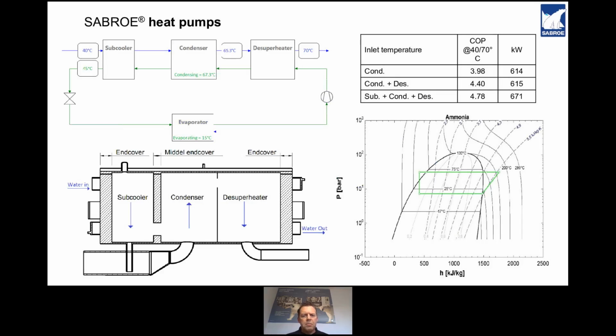So moving on to the next slide. How does it work? Here we go. Lots of diagrams, I apologize. Top left is the diagrams to look at. If you look at we have the compressor, the circle with the diverging lines on the right hand side of the top left diagram. We have that discharging hot discharge gas at about 130 degrees C. That enters the desuperheater, where it loses a lot of its heat down to about 67 degrees. The middle heat exchanger, the condenser, and finally the subcooler takes the last bit of the heat out of the gas. So this is all in one heat exchanger, quite tidy.